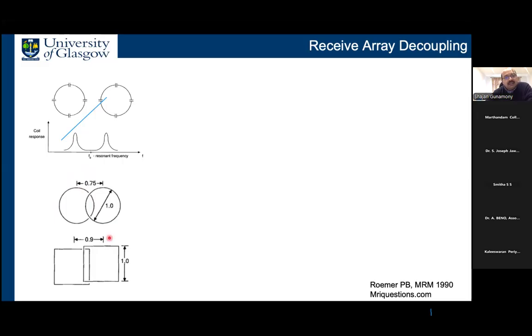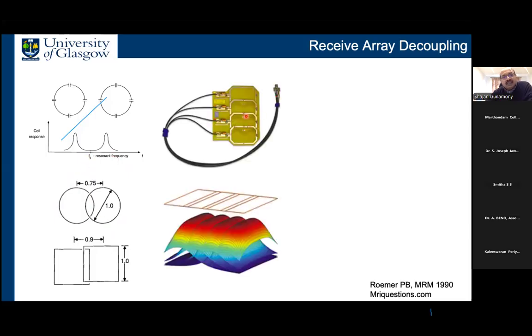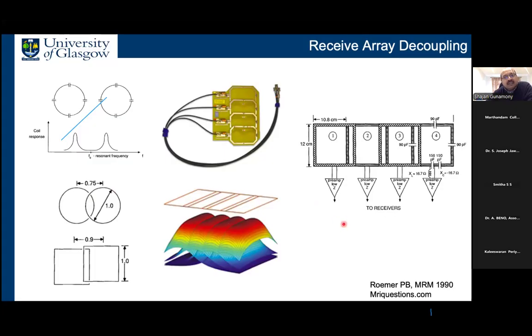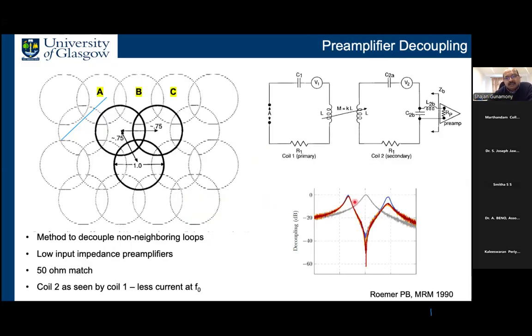But you can overlap these loops to a point called critical overlap, at which the mutual inductance is 0. So then you get away from this split resonance and you create a single resonance. So in this example, you can see there are 4 loops. They are overlapped using this method. So the combined image will have a higher sensitivity, which is spread over a larger volume. So these are then connected to preamplifiers, and that amplifies because the MR signal is really, really weak, and so you need to amplify this signal before it is down converted and then digitized. So if you geometrically overlap the loops, then they have to be adjacent to each other.